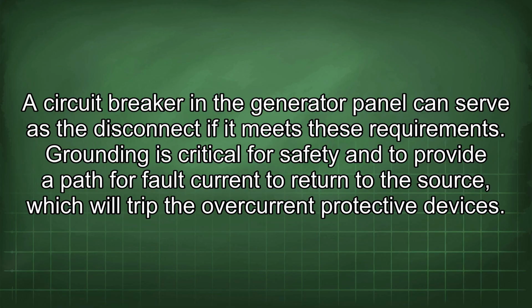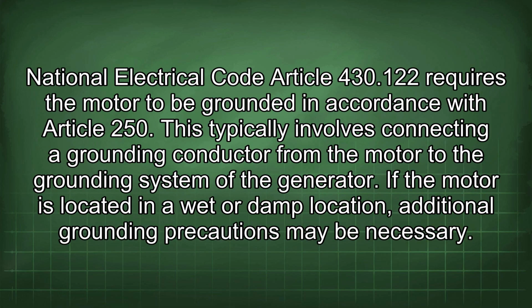Grounding is critical for safety and to provide a path for fault current to return to the source, which will trip the overcurrent protective devices. National Electrical Code Article 430.122 requires the motor to be grounded in accordance with Article 250. This typically involves connecting a grounding conductor from the motor to the grounding system of the generator. If the motor is located in a wet or damp location, additional grounding precautions may be necessary.